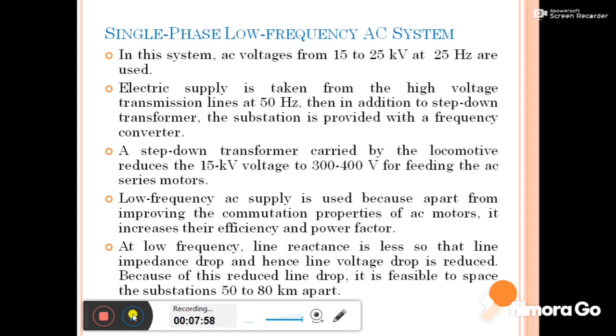So why are we going for a low frequency instead of 50 Hz? At low frequency, line reactance is less. As we know, the formula is XL equals 2 pi FL. If the frequency is less, XL will reduce, then the impedance drop will be less, and the line voltage drop will reduce. Once that reduces, it increases the efficiency of the system, meaning we can maintain the same voltage from the sending end to the receiving end.